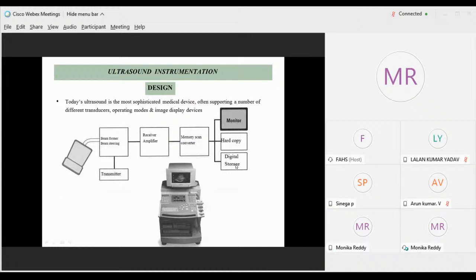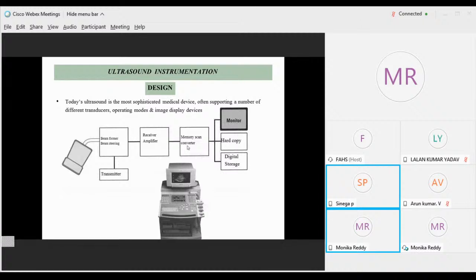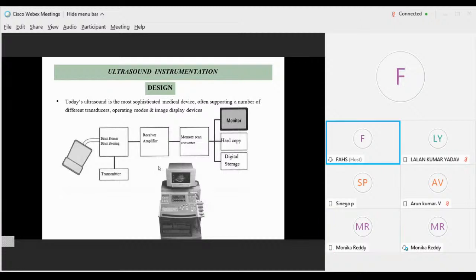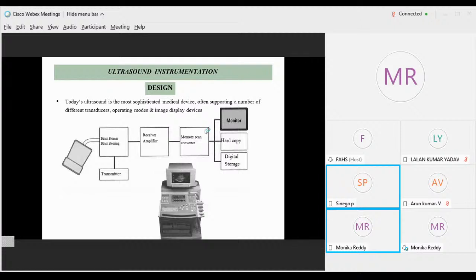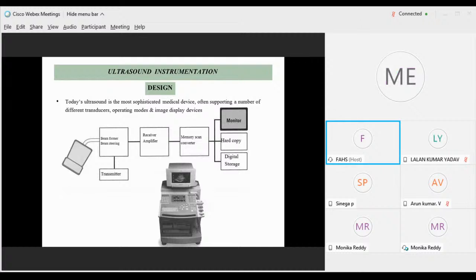Here you can see the block diagram. It starts with the transducer and ends with the image display on a monitor, or storage as hard copy and digital storage. In between there are the beam former, which will steer the beam, the receiver, amplifier, memory scan converter and pulse transmitter. These are the inbuilt parts inside the ultrasound machine, which all together take part in the image formation.